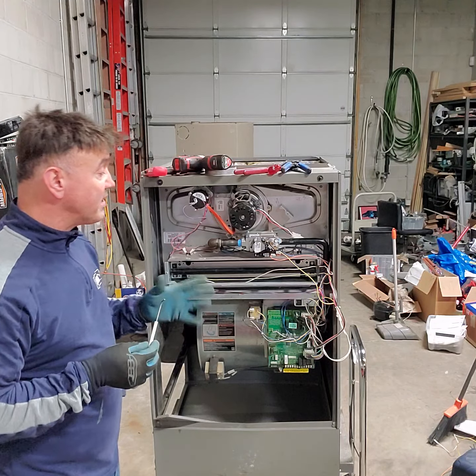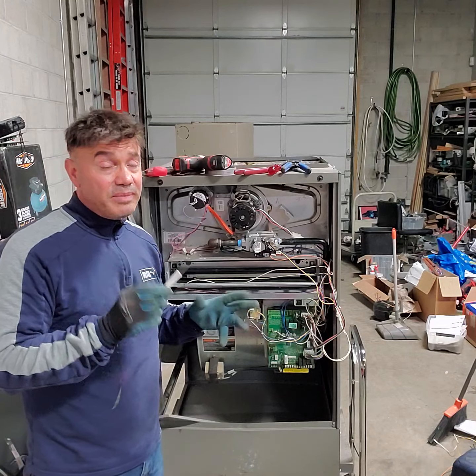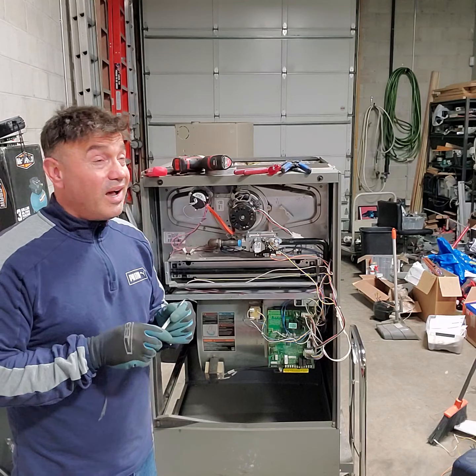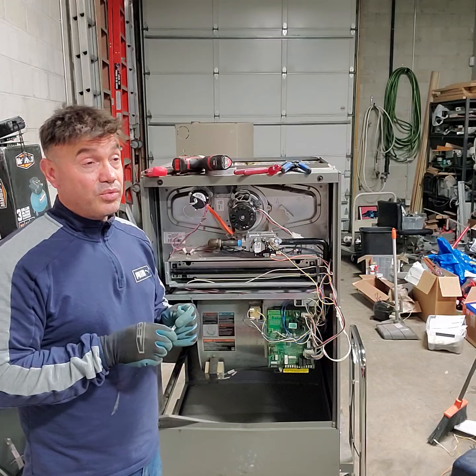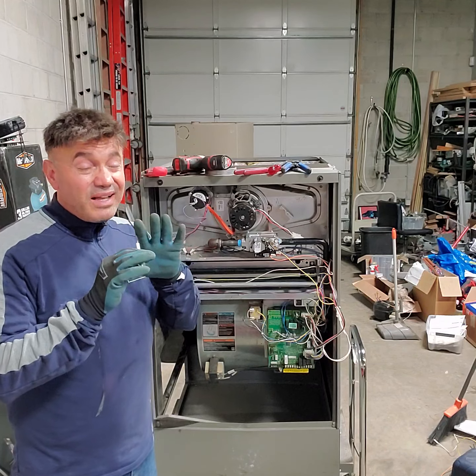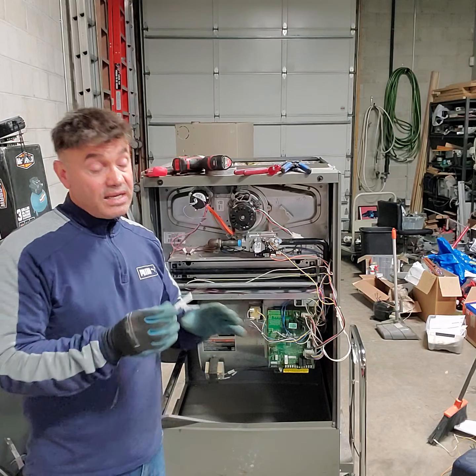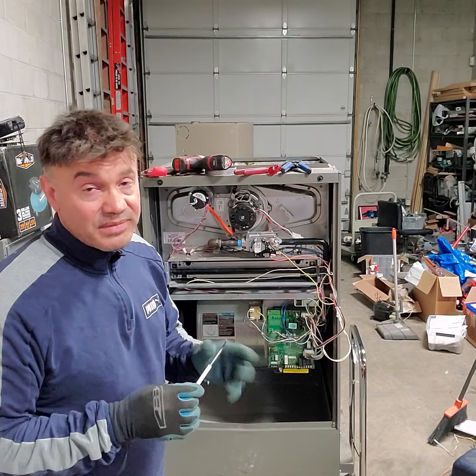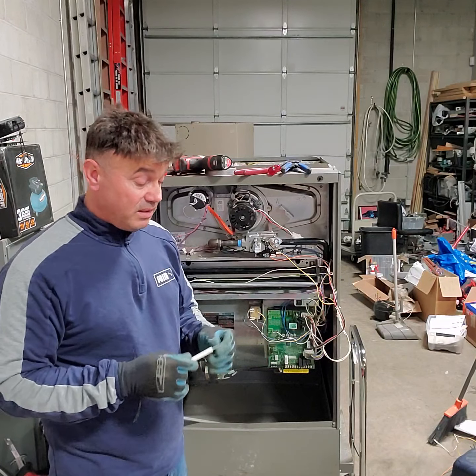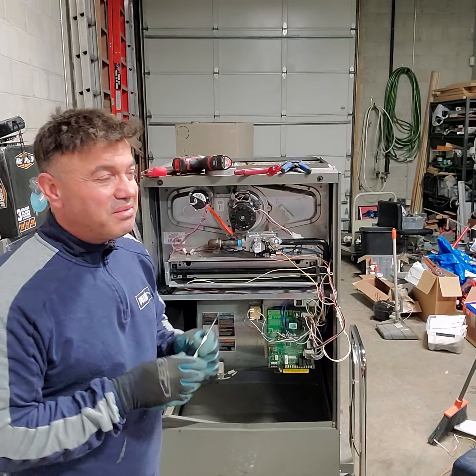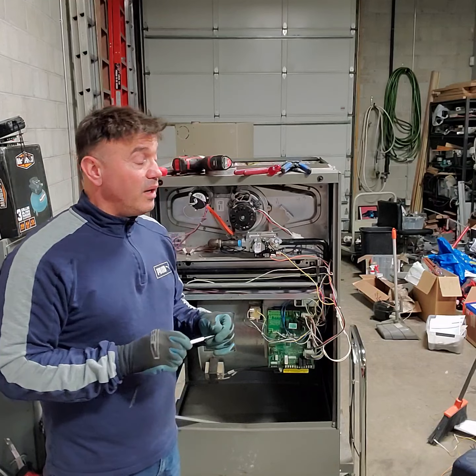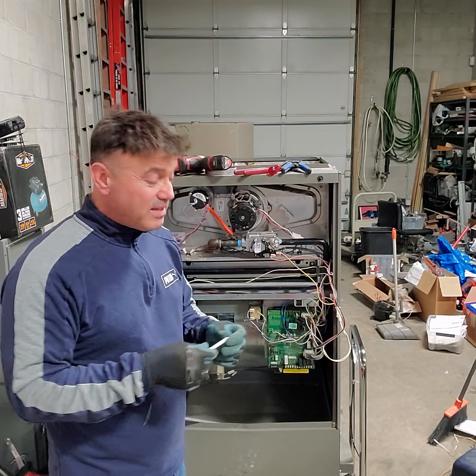Now, how to fix it? The biggest problem with the flame sensor is people think it's bad. Honestly, I've been doing this for 26 years, and I rarely see a bad flame sensor. Usually it's not bad, they very rarely go bad.